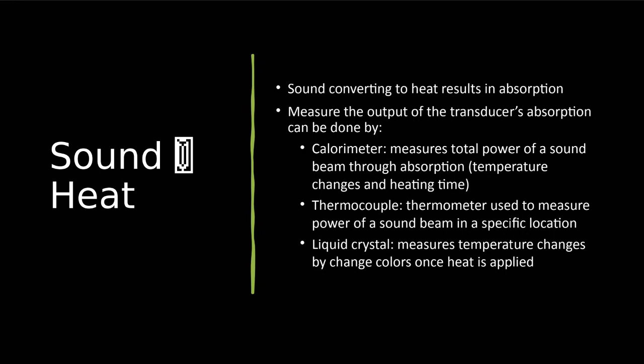We can also use a thermocouple. This is a thermometer used to measure power of a sound beam in a specific location. We can also use a liquid crystal, and when this crystal is heated up, it's going to change its color. So we can evaluate the color of that crystal depending on how much temperature change had occurred. Again, not something that you guys will probably ever see. I've never seen any of these bioeffect tests being done. So just something that you need to be aware of.